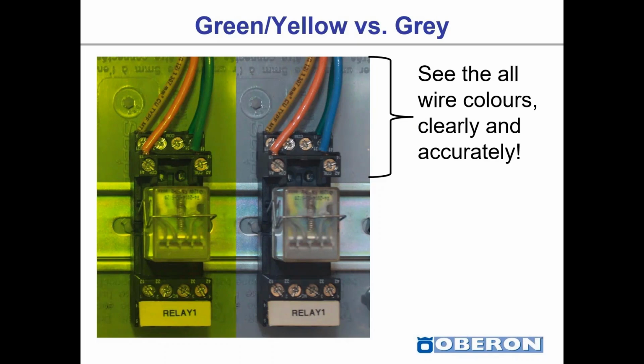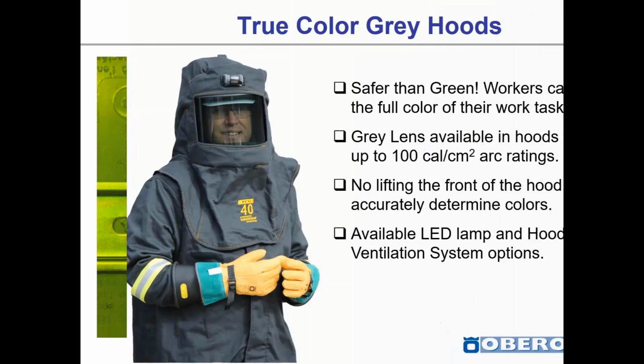An example of that would be this little scenario I built here, which is a relay with some different colored wires. On the left-hand side, if I ask you to identify the green wire and the blue wire, it shows that the green wire is in front and in the back is the blue wire. However, if you look through a gray face shield, which provides true color acuity, or true color perception, you have the green wire in the back and the blue wire in front. So we could easily see using this example how mistakes could be made by wearing traditional arc flash PPE, and the new technology allows us to see clearly and accurately.